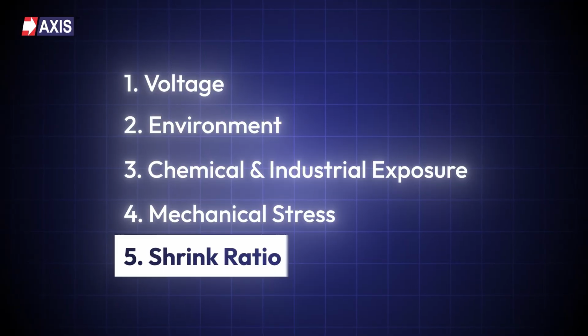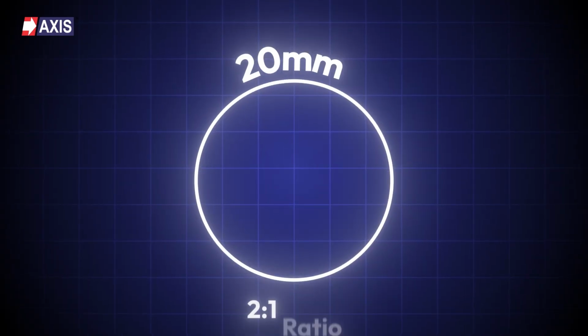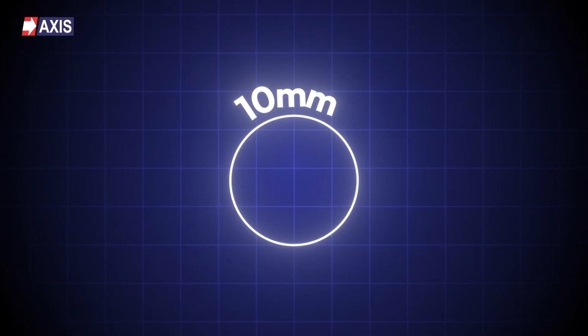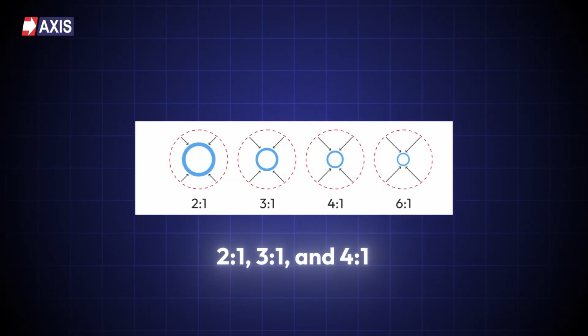Lastly, the shrink ratio. This ratio tells you how much the tubing will reduce in diameter after heating. For example, if you take a 20 mm tube with a 2:1 ratio, it will shrink down to about 10 millimeters. Similarly, a 3:1 ratio means it will shrink to 1/3 of its expanded size. This is important because in real-life installations, your cables will not have the same diameter everywhere you go. You will have lugs, connectors, or joints where the diameter will increase. The tubing must pass over the largest part and then shrink tightly over the smallest one. Some common shrink ratios are 2:1, 3:1, and 4:1. These ratios affect installation ease and long-term reliability.